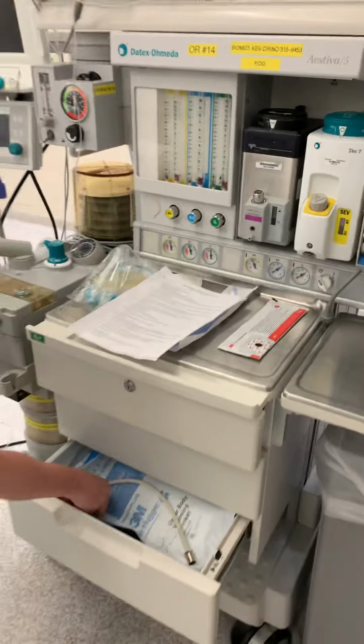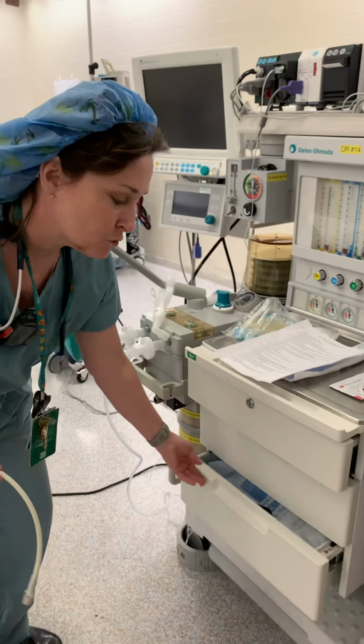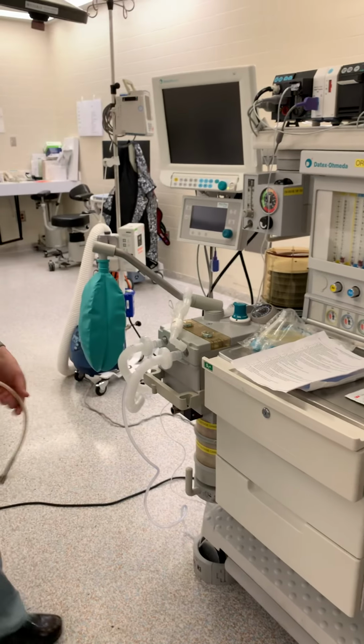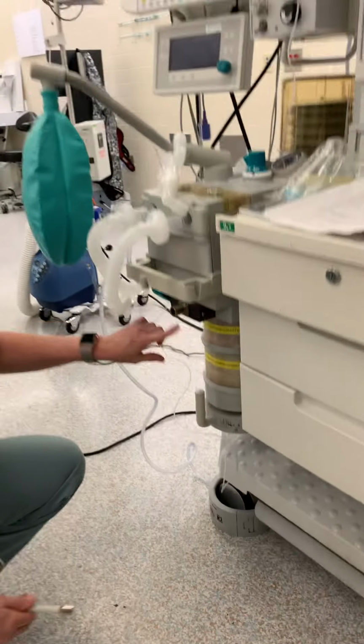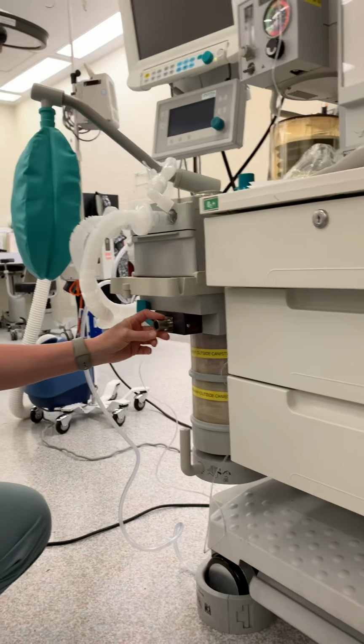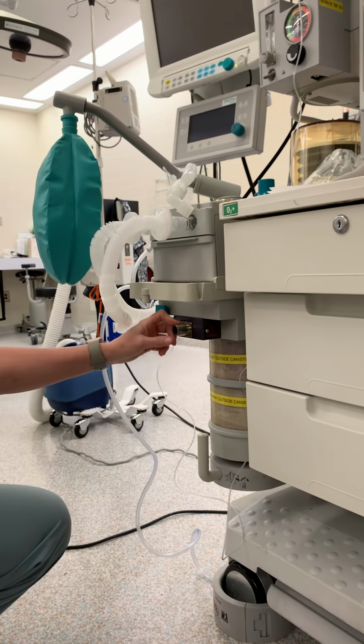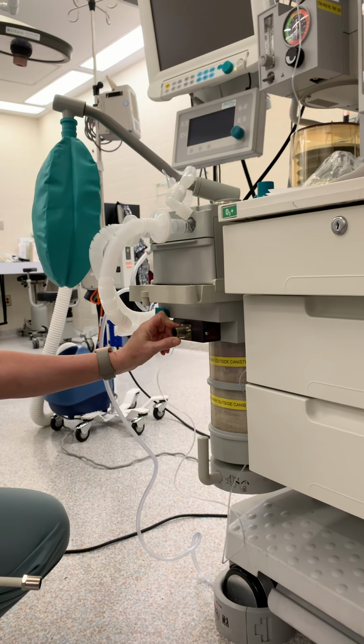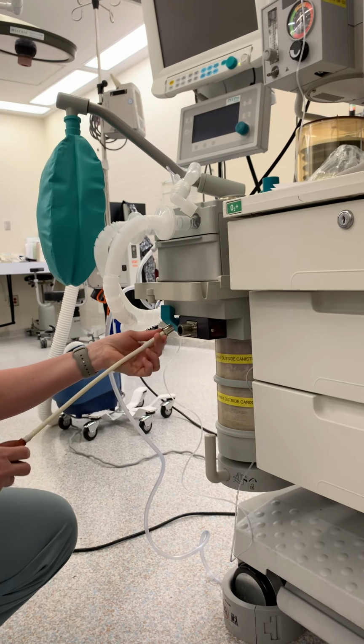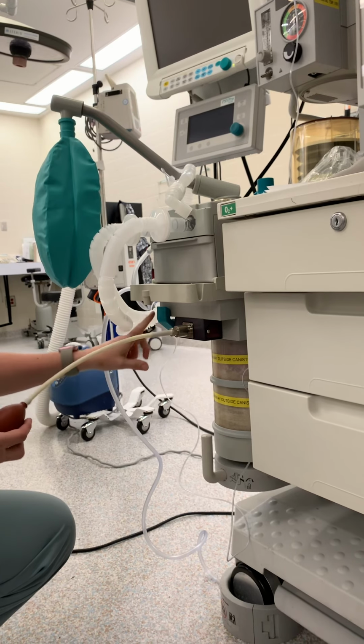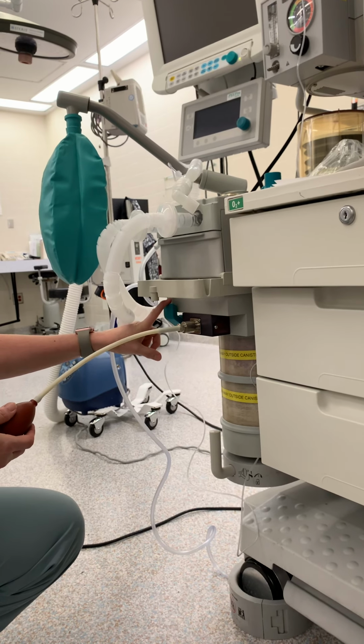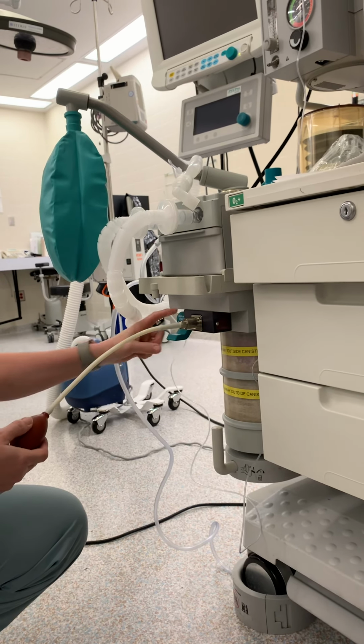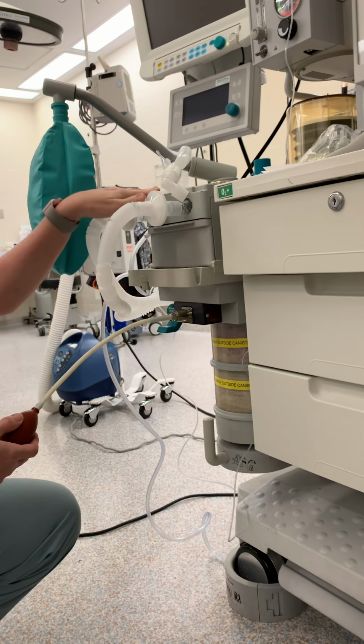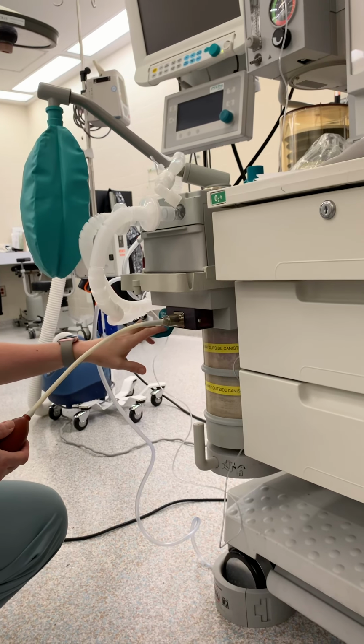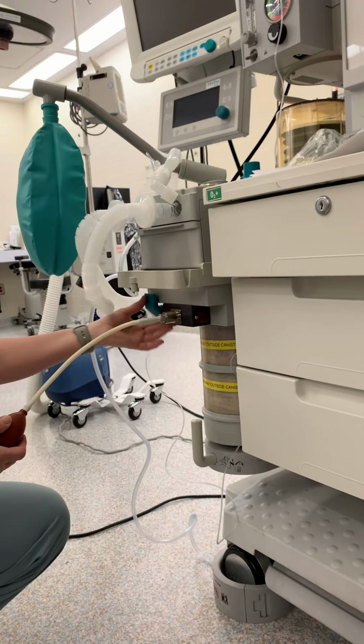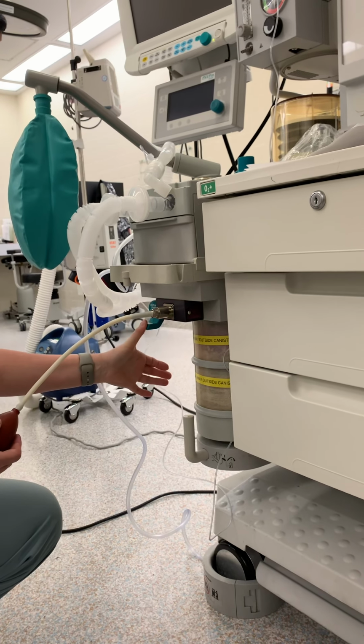Now we will get out our bulb suction. It's located in the bottom drawer of most machines. You want to identify the common gas outlet on this machine. It's here. It can also be known as the auxiliary common gas outlet, and you can see the attachment will go straight in. You need to switch functioning to the common gas outlet and away from the machine. You do that by a switch. The switch is right here on this machine, and you pull down.